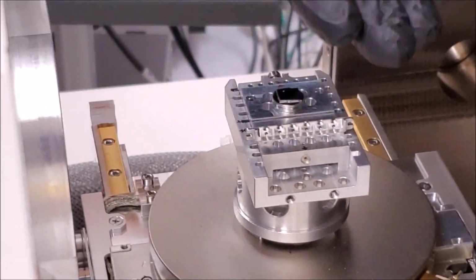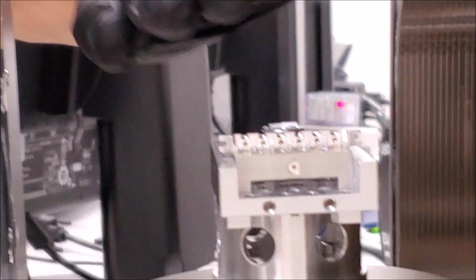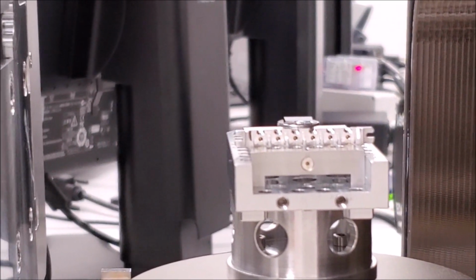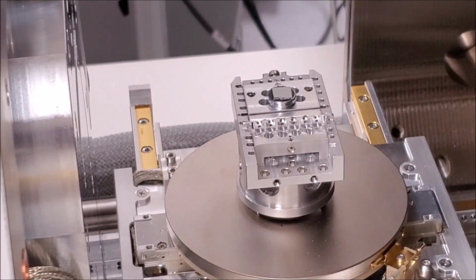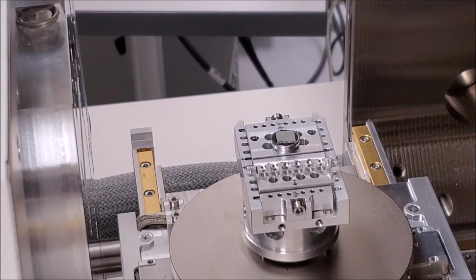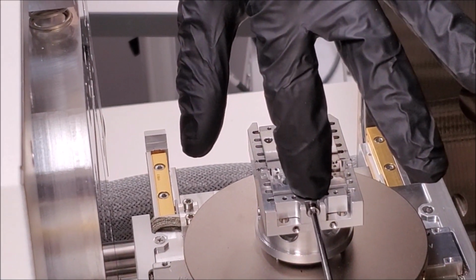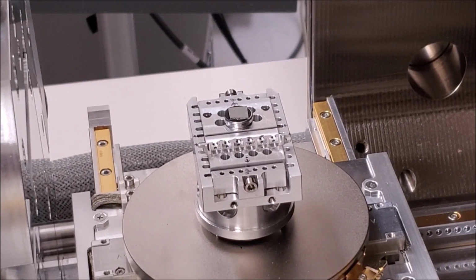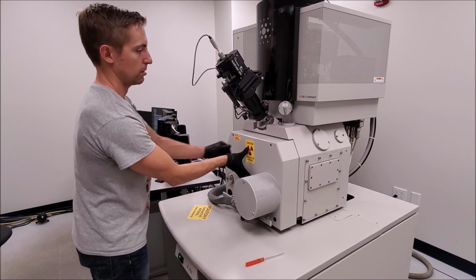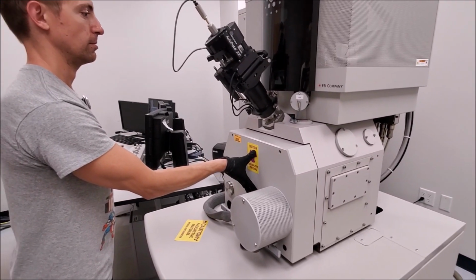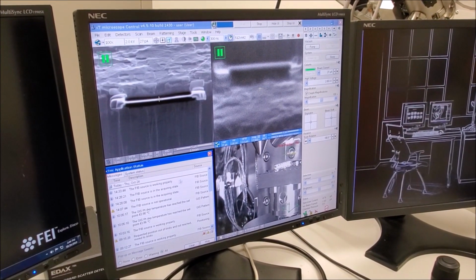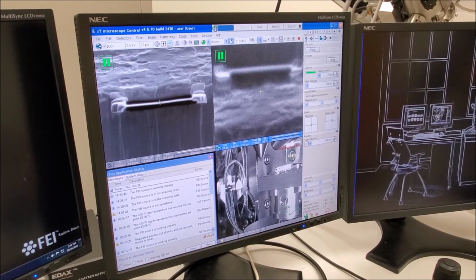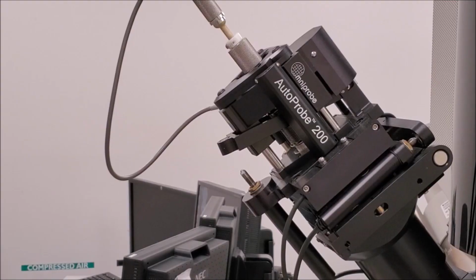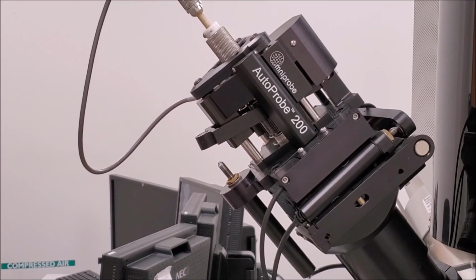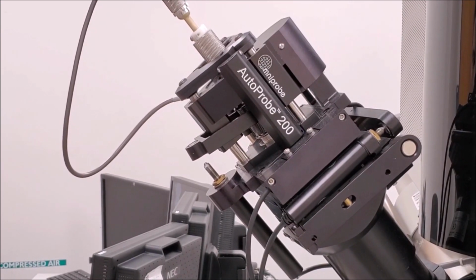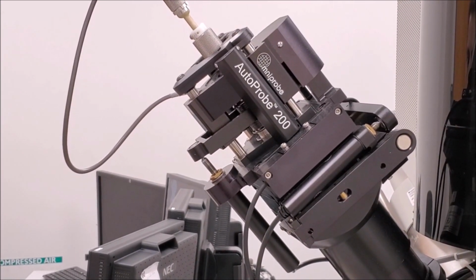When you load the grid holder into the module, make sure that it is level. Then place the remaining clamping bar and tighten it down. Gently close the chamber door, making sure it is completely flush with the edge of the chamber. While maintaining pressure, once the hinge is fully closed, pressure on the chamber door does not need to be applied anymore.